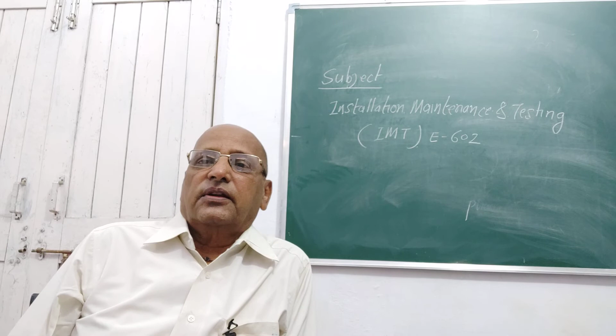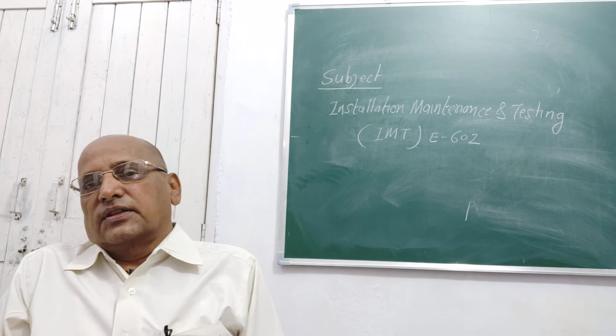Which are having rating. Definitely, I have told you that above 5 kilowatt or 5 HP, or big generators in terms of megawatt capacity, their installation is slightly difficult, because balancing is required. In this case, balancing of the rotor is to be done on the site. So there are separate equipments required for the rotating machines, apart from chain pulley block and other cranes. We require a rotor balancing system, which is used for balancing the rotor when it is to be kept inside the stator after installation on the site.